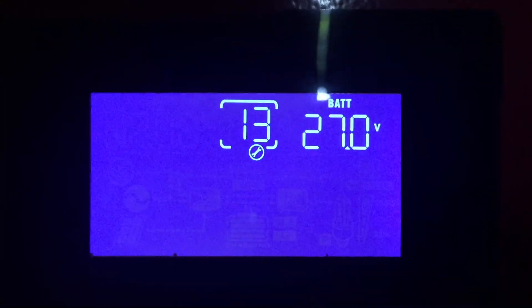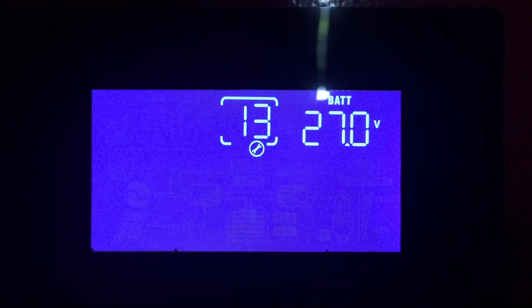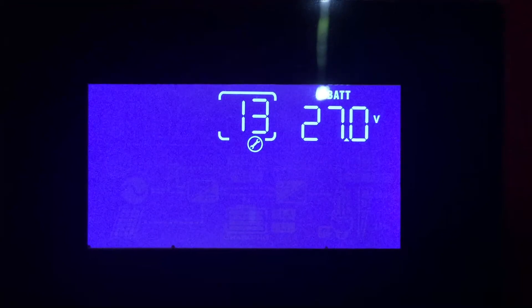Number thirteen is kind of the opposite. In this particular case once the battery has gotten a fairly good charge when do you want the unit to start using battery again. Say for instance if the sun is not shining and you're not getting anything from the PV when do you want it to use the battery again.